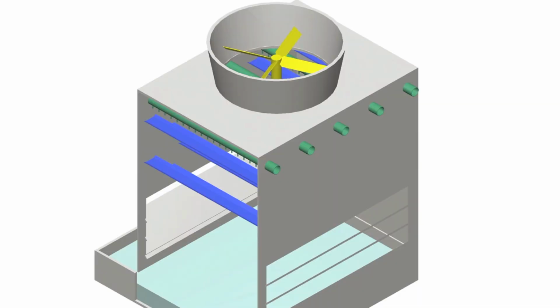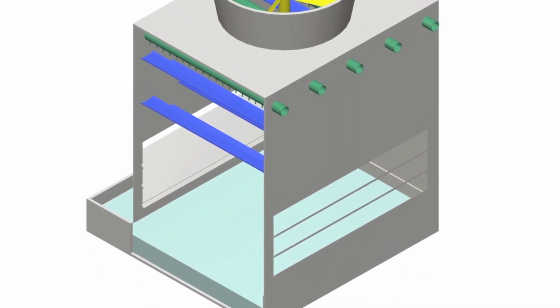So you can electronically see where the water level is if you're having an issue with high water or an issue with low water, or if you want to see the fill switch happening, you can monitor all that through these dry contacts on this particular controller. So you don't have to walk out to the cooling tower anymore and physically look in it. If you had a mechanical float, that's what you'd have to do. You have to go out there and physically look at it to see: is it overflowing, is it too low, is the mechanical float switch working properly?